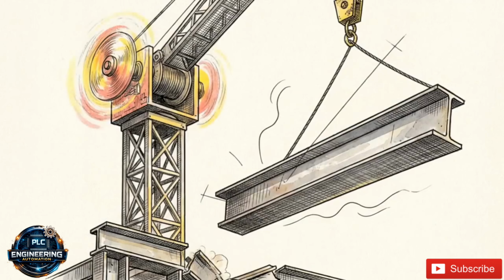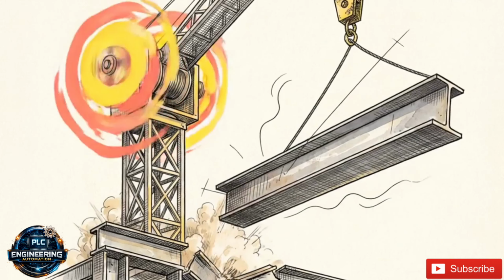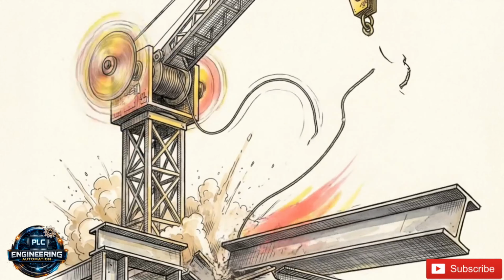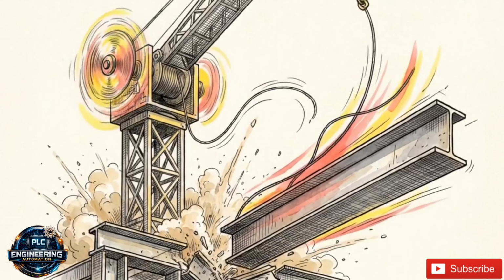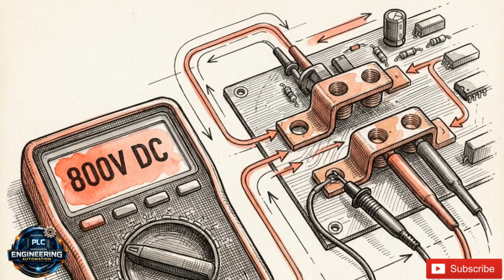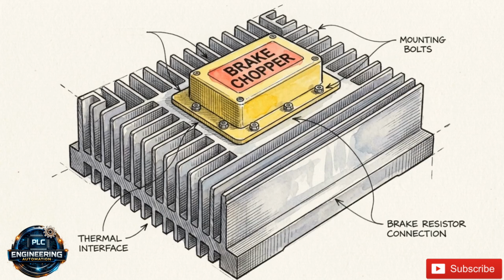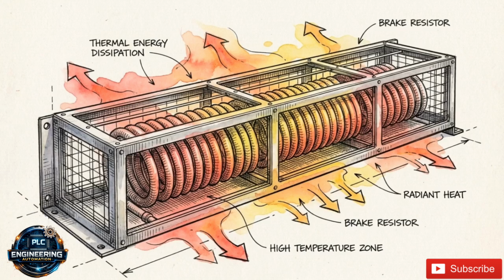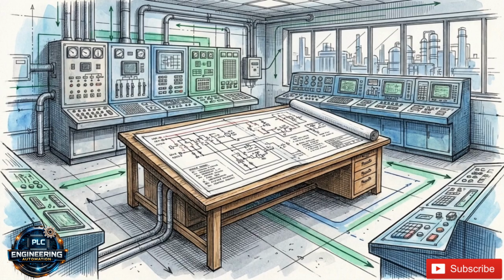Then there is the threat of mechanical regeneration. When a heavy load, like a descending crane, pushes the motor, gravity turns it into a generator. Electricity flows backward into the VFD, causing the internal DC bus to rapidly spike toward a critical 800 volts. To prevent the internal capacitors from rupturing, a built-in brake chopper activates. It redirects this regenerative energy outward into a heavy-duty brake resistor, where the excess power is safely burned off as heat. These external components are not optional accessories.